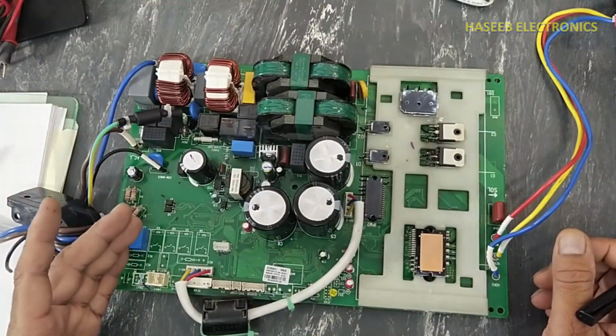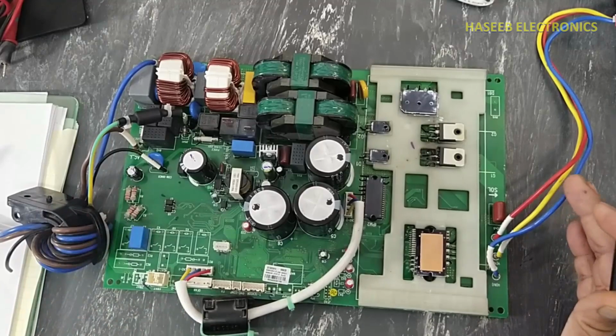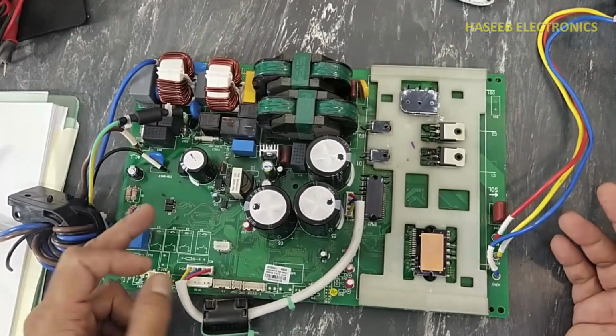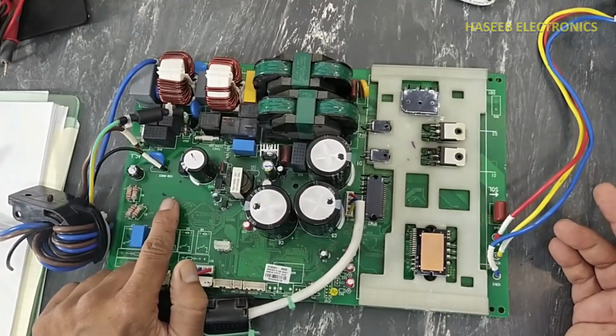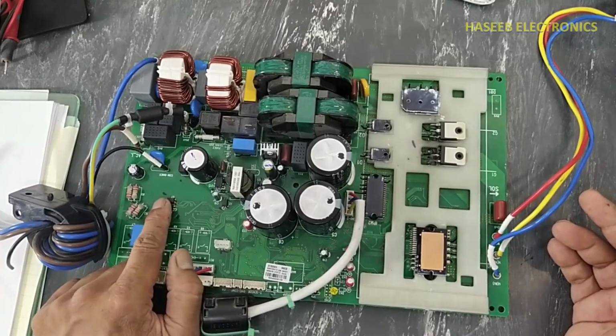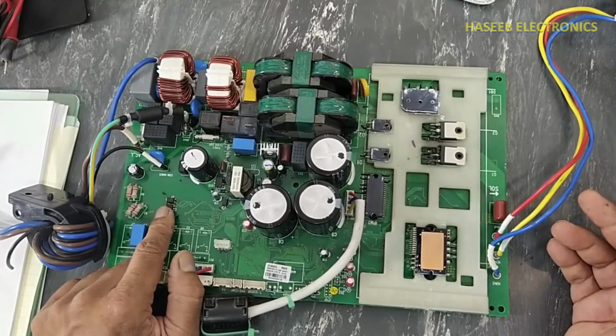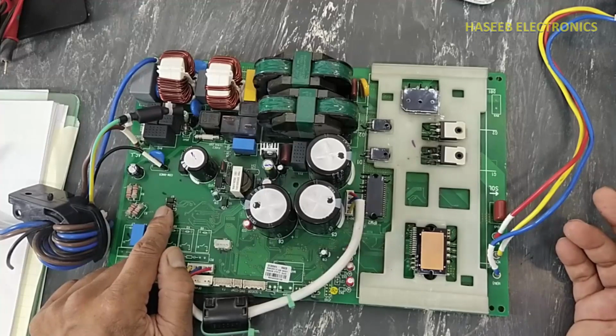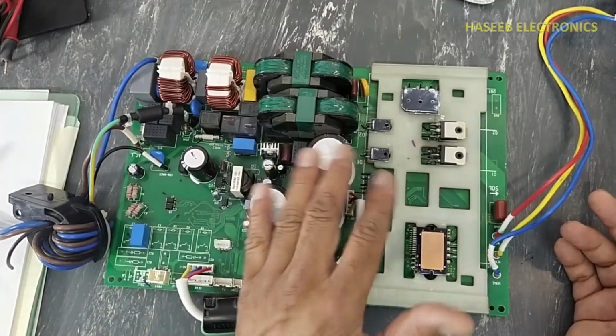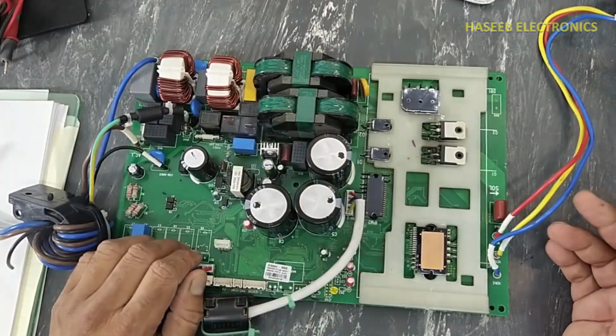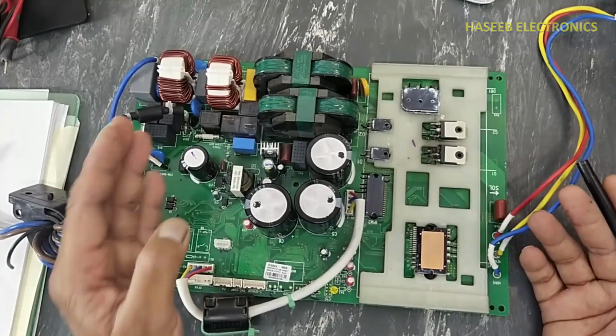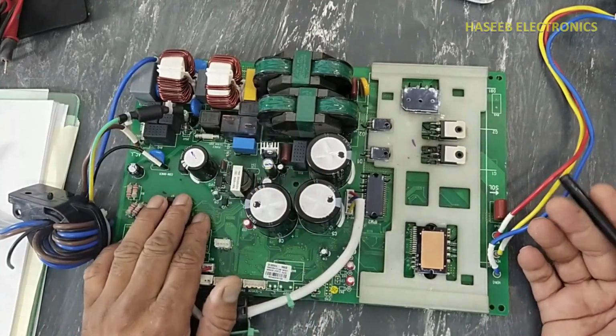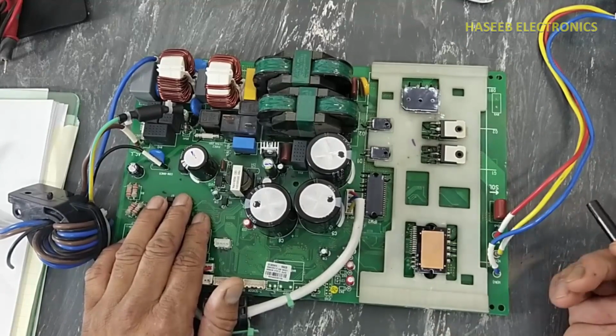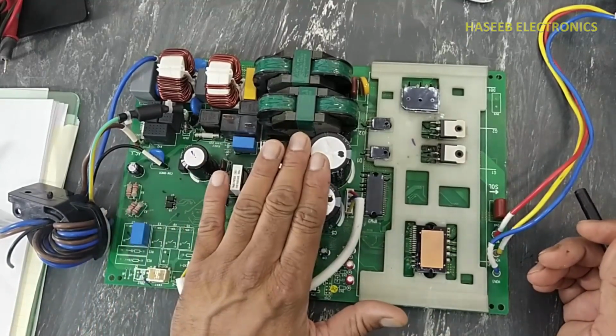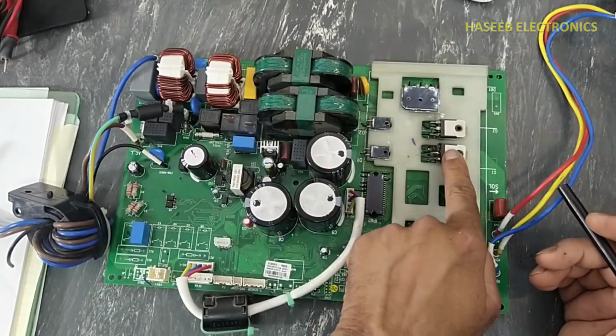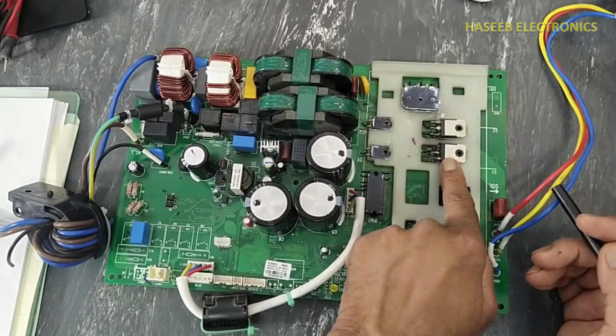Most commonly when we find a communication error, our first checkpoint is these optocouplers. When the transmission or reception optocoupler is bad, the board will not respond to the indoor unit. But sometimes there are other faults other than these optocouplers. The same here. In this board, we found this IGBT short circuited.